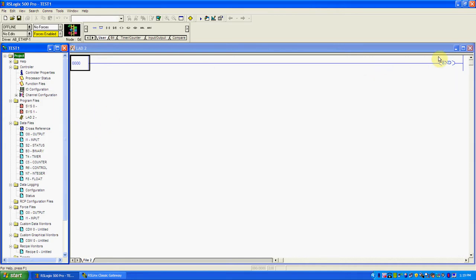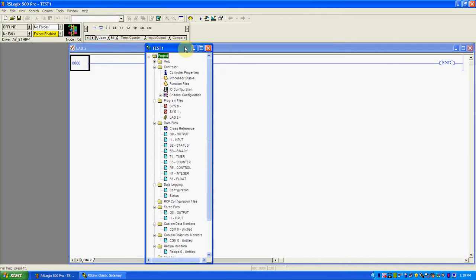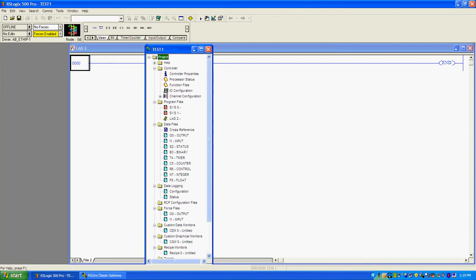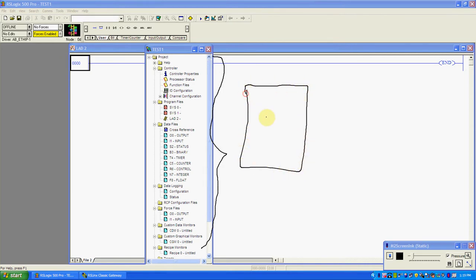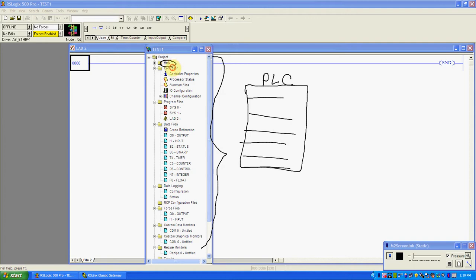We have a new program now. It defaults with Ladder 2 open — I'll explain what Ladder 2 is in a second. If I open up the project tree, you'll see what I've slid over here — all the stuff contained in this folder. Imagine it as basically a big block of memory — this whole block is all of the PLC memory, sort of like a C drive in a computer. They've divided it up into sections. These are all folders, and this stuff is files contained inside the folders. In the data files folder you have all the data files — this is where all of the I/O, internal bits, timers, and counter memory is stored, and we reference this in our program. In program files is where Ladder 2 exists — that's where your ladder logic goes.